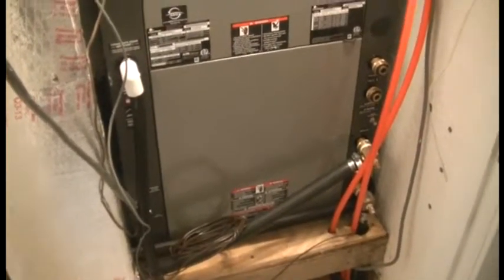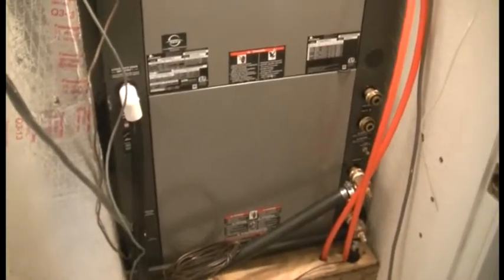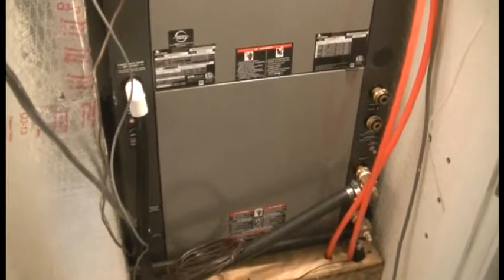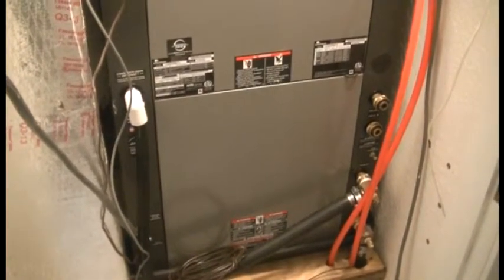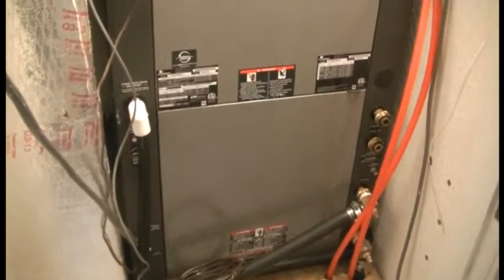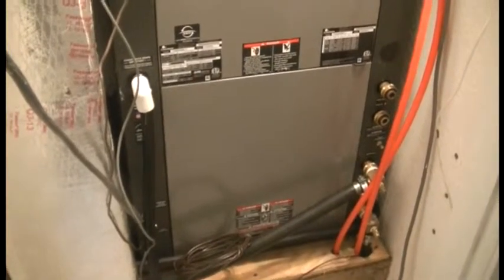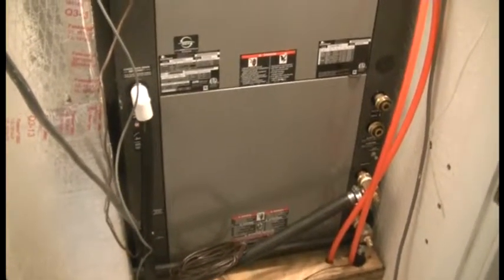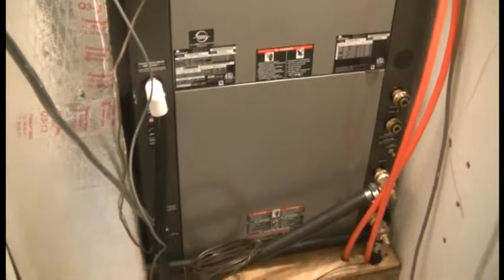We have not yet hooked up the desuperheater lines, which we will shortly. But those will provide all of the hot water that is needed, and basically they just use the high temperature water off the early coils of the heat exchanger to pump very hot water into the hot water tank, so you're using the geothermal energy for heat. This unit is very efficient. I measured it at a little over 26, and I'm very pleased with that.